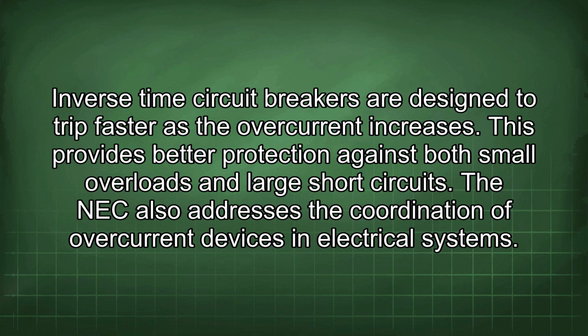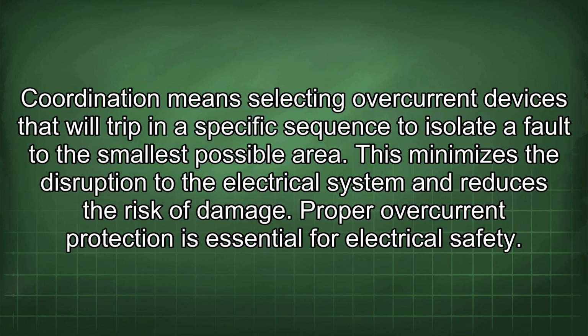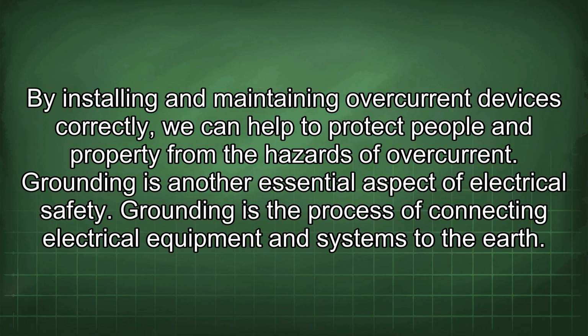The NEC also addresses the coordination of overcurrent devices in electrical systems. Coordination means selecting overcurrent devices that will trip in a specific sequence to isolate a fault to the smallest possible area. This minimizes the disruption to the electrical system and reduces the risk of damage. Proper overcurrent protection is essential for electrical safety. By installing and maintaining overcurrent devices correctly, we can help to protect people and property from the hazards of overcurrent.